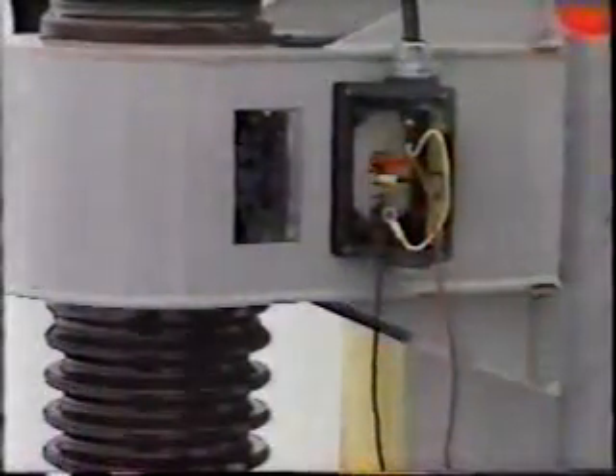In some installations, the CT is fitted with a test winding specifically for primary injection. In other cases, a temporary primary can be fed through the CT donut for test purposes. Before commencing any primary injection test, make sure that the primary circuits are isolated and available for test purposes. Take out a permit to test from the operators. You will probably have to remove grounds from the primary circuit. When applying the test connections, make sure that they make good contact, or you may get unreliable results.